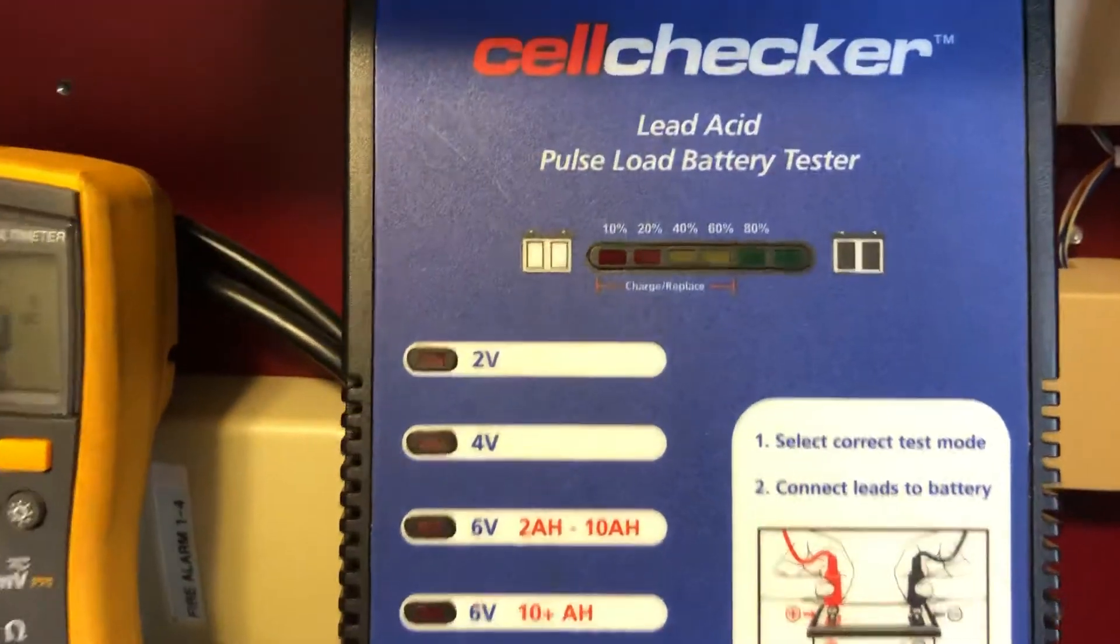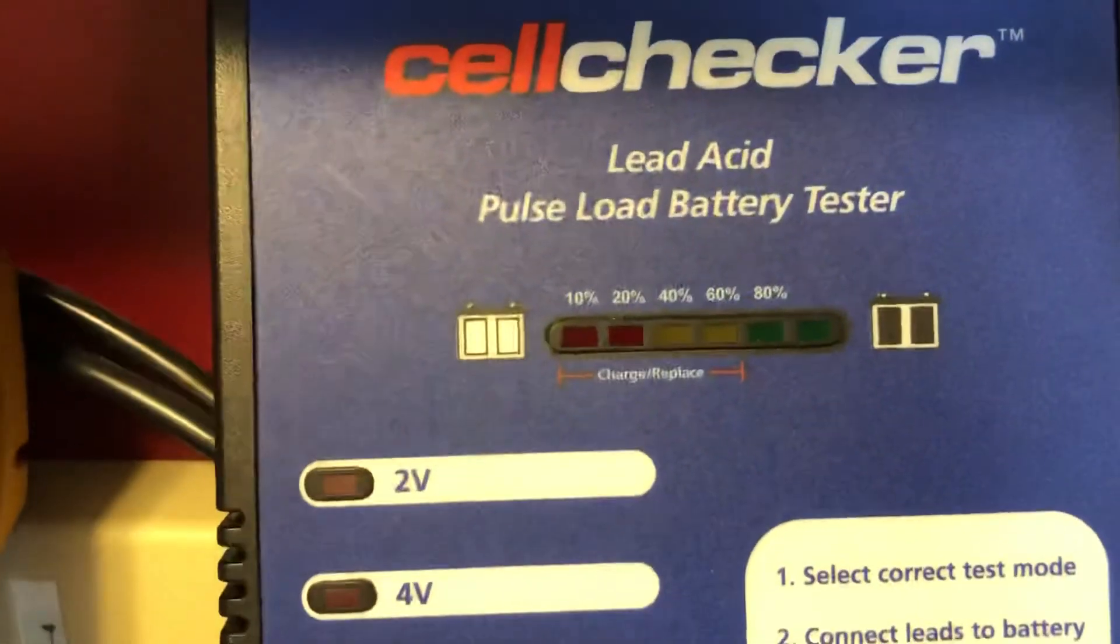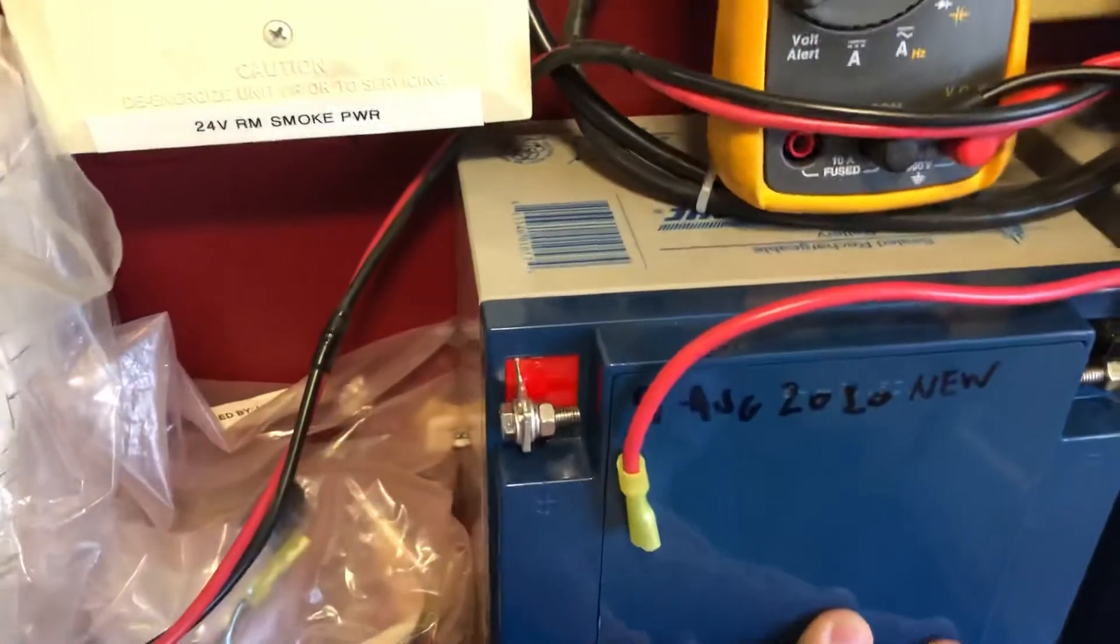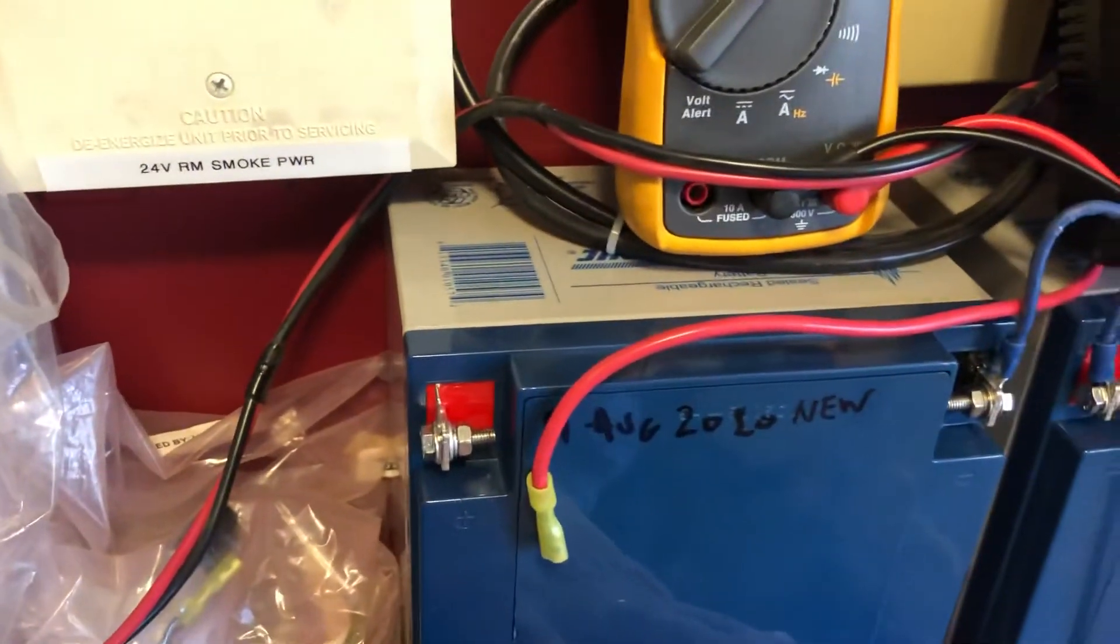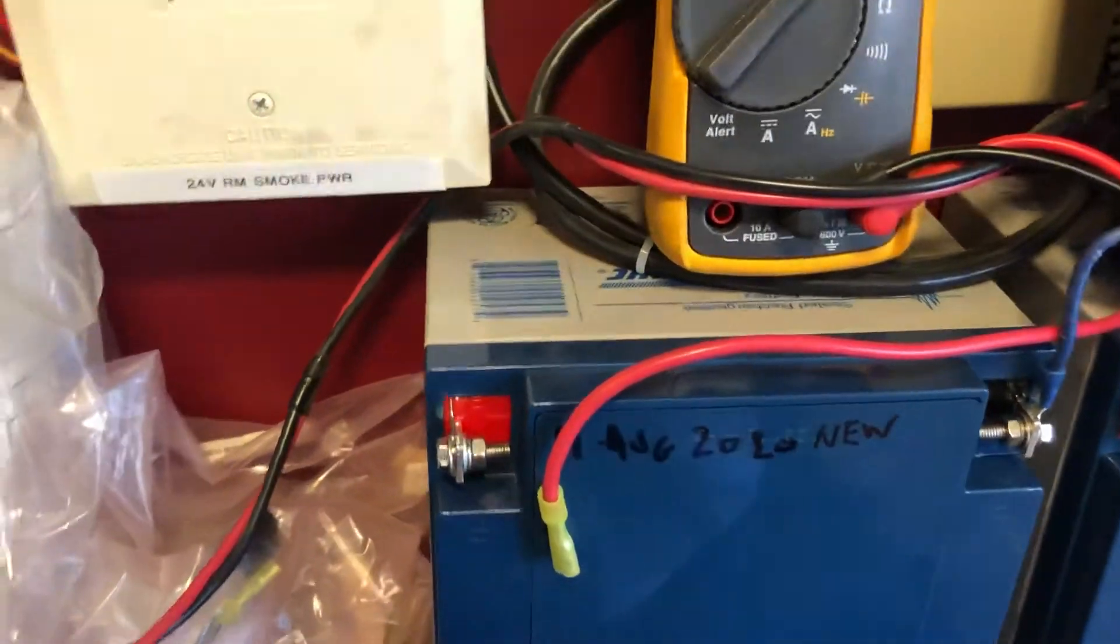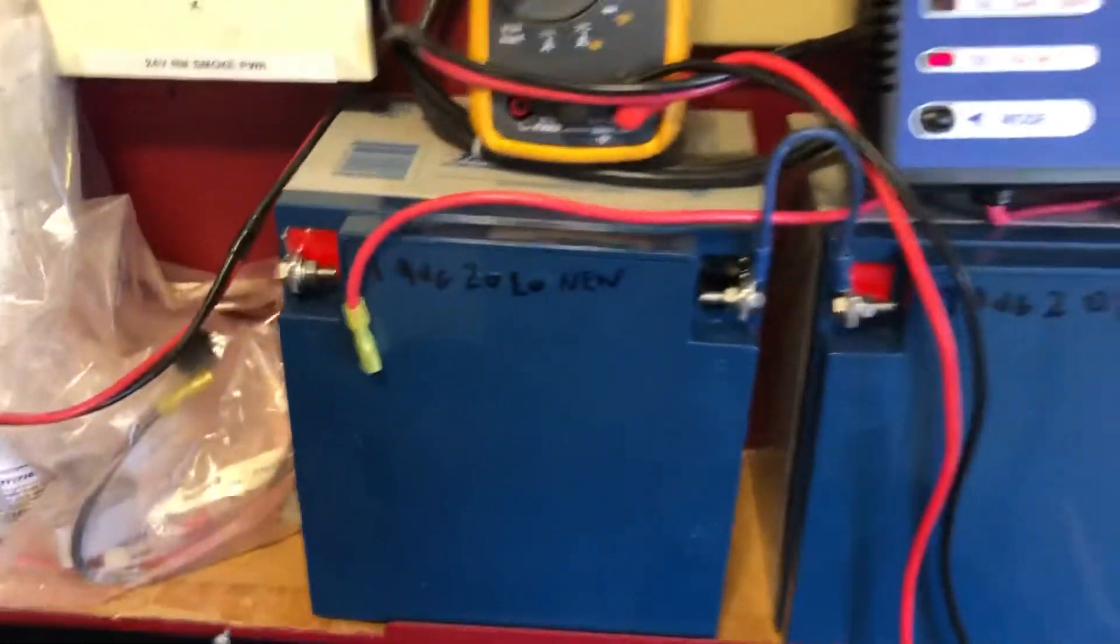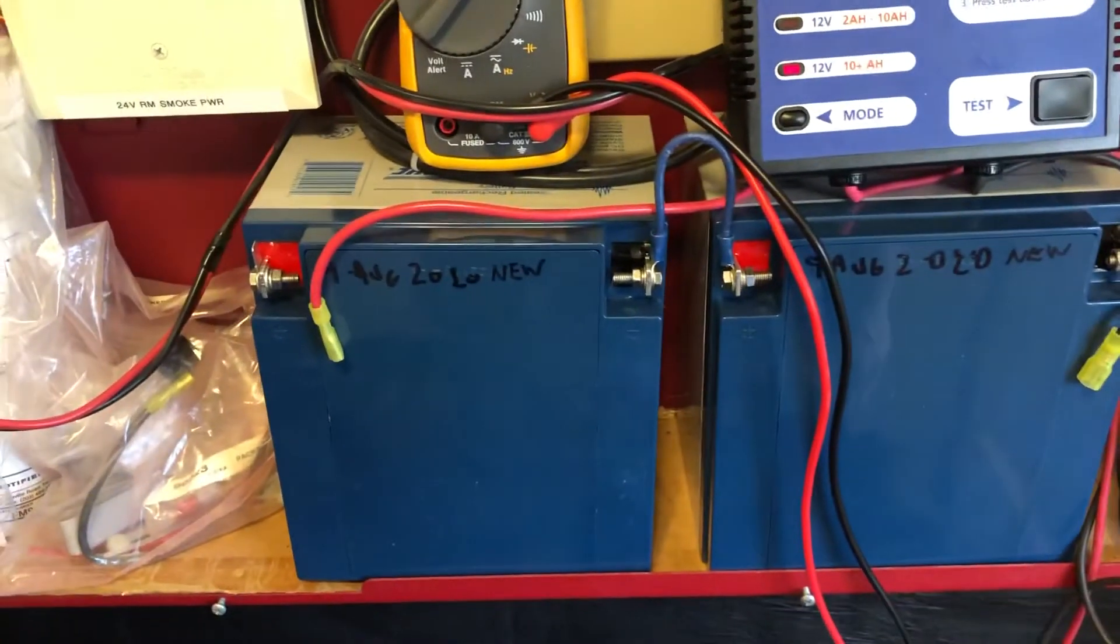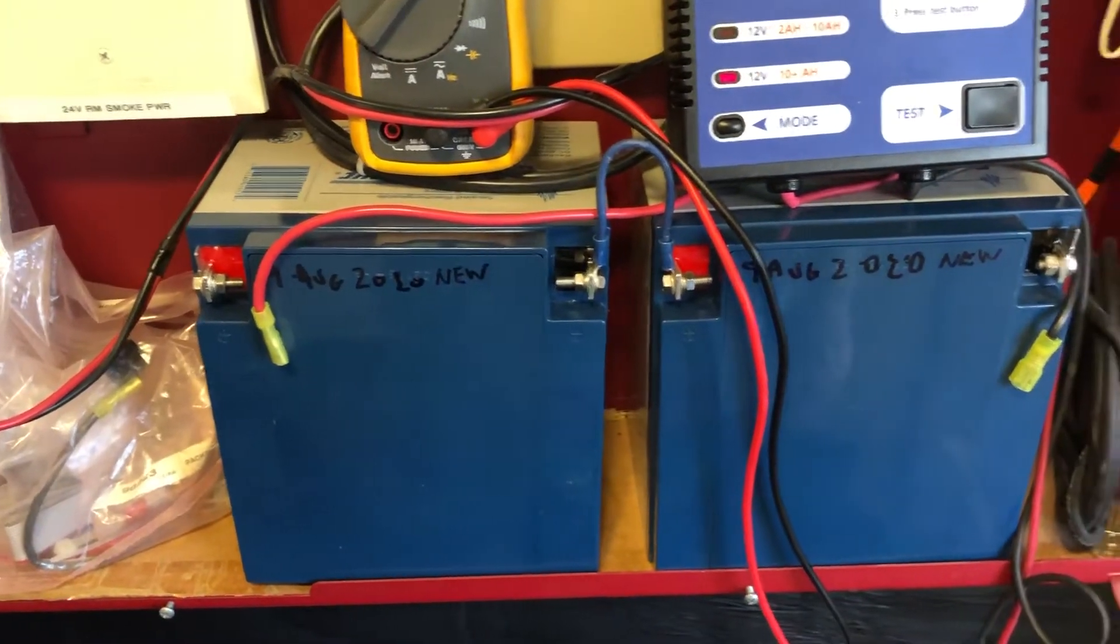You basically want to, when they get down to 60% of the value, these are 24 or 26 amp hour batteries, when you get to about 60% of that, you should replace them.